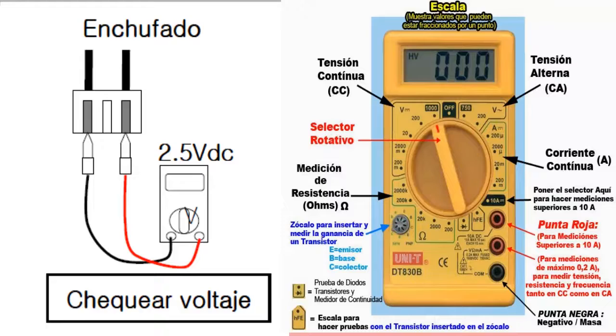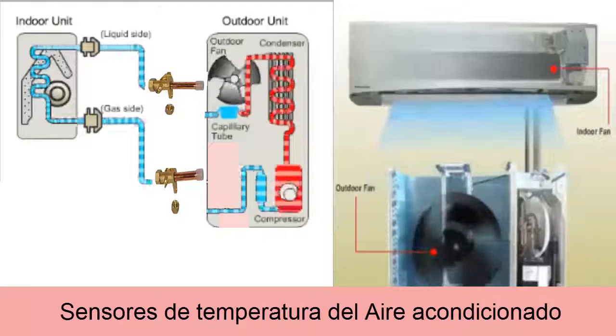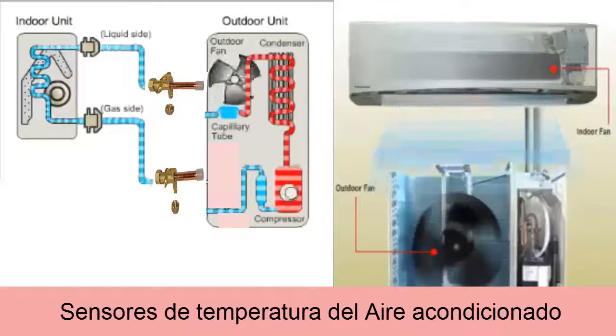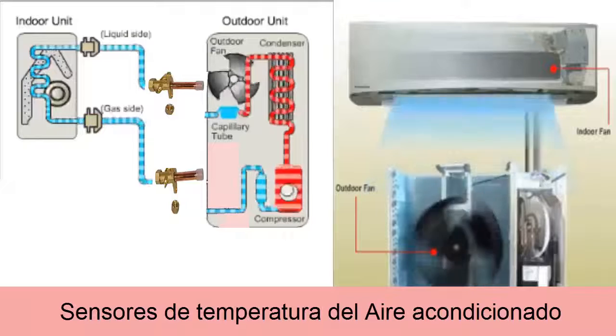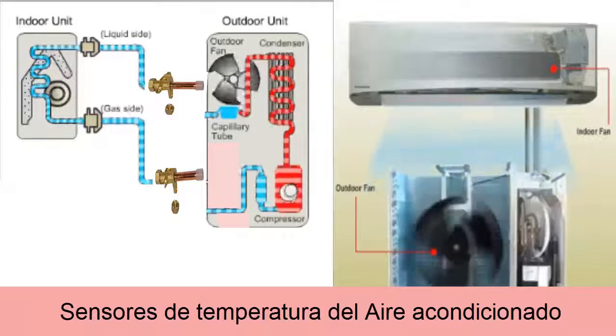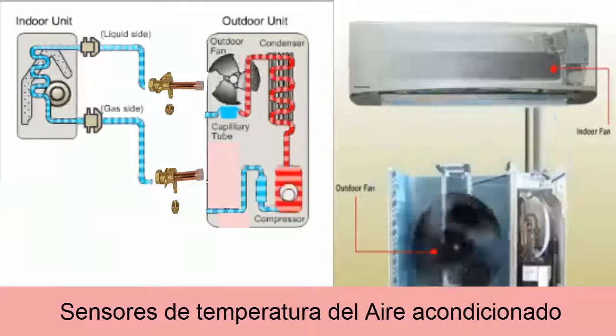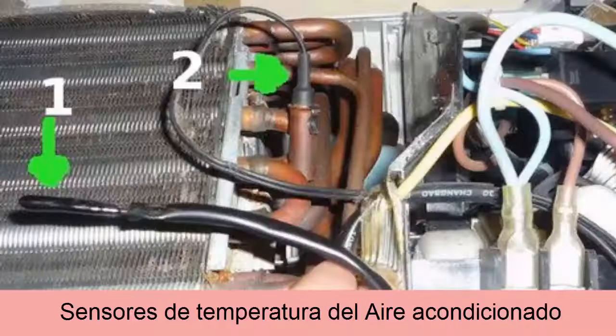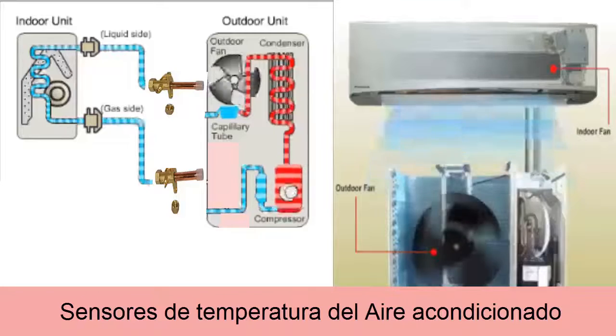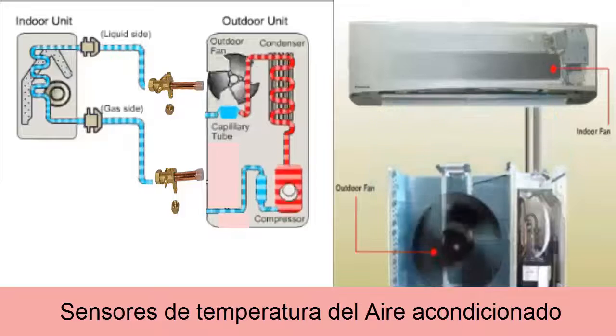These would be the steps to diagnose the sensors. When we talk about the types of sensors, we are going to find the local temperature sensor, which measures the temperature of the return air to average the temperature of the enclosure we are air conditioning. When there are problems with this sensor, you will mostly find the failure codes E4, E2, and E1.